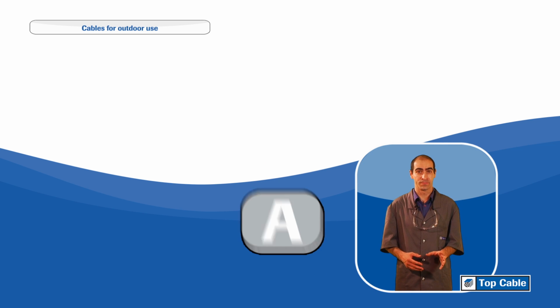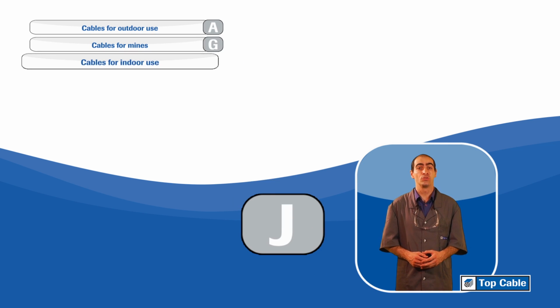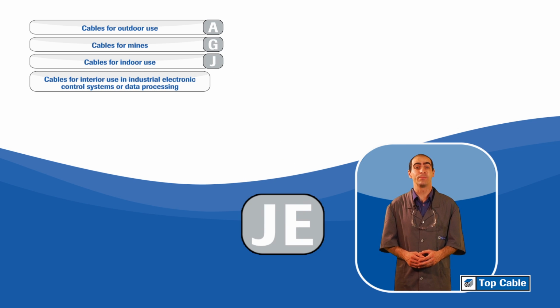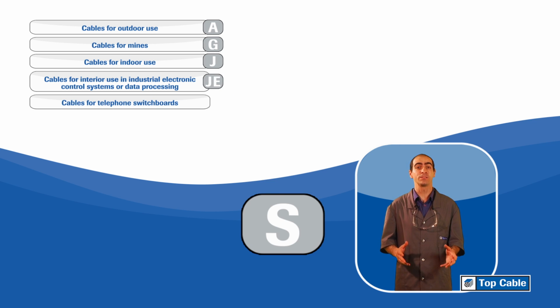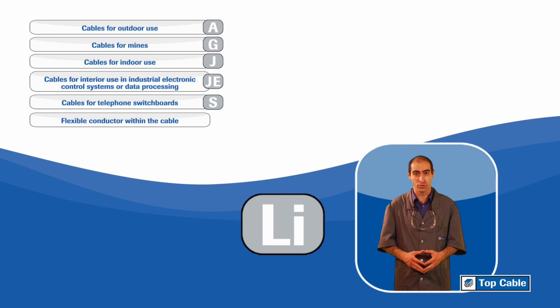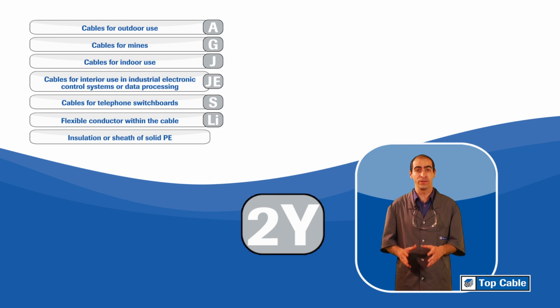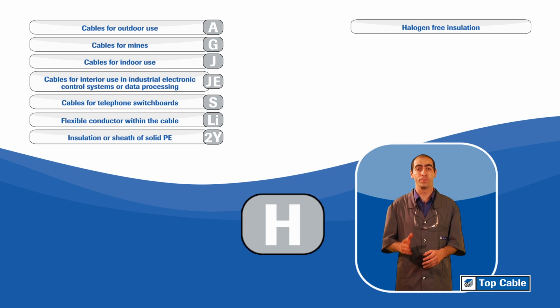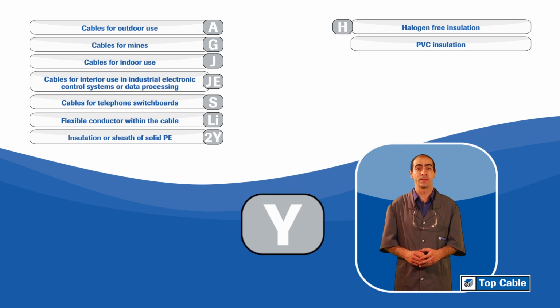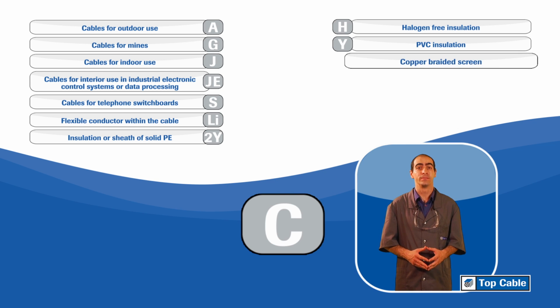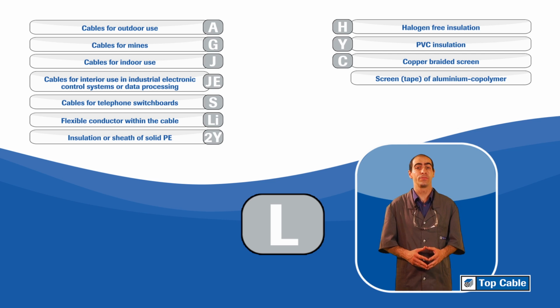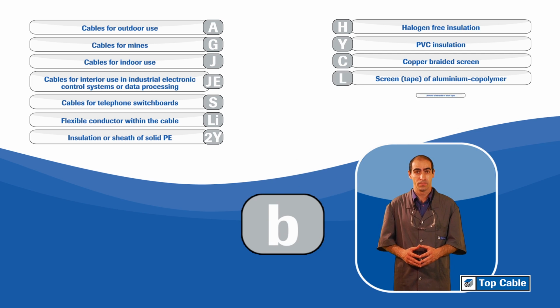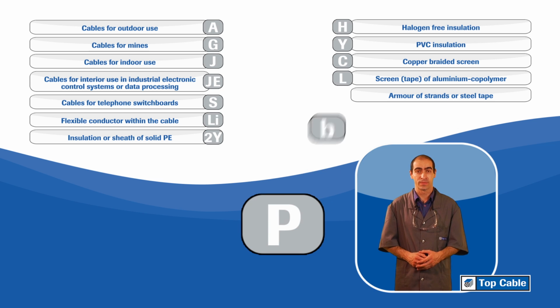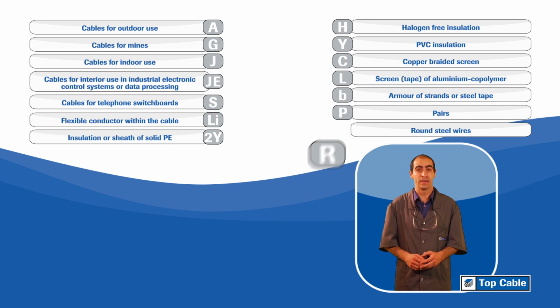The most common letters mean: A, cables for outdoor use. G, cables for mines. J, cables for indoor use. JE, cables for interior use in industrial electronic control systems or data processing. S, cables for telephone switchboards. LI, flexible conductor within the cable. 2Y, insulation or sheath of solid PE. H, halogen-free insulation. Y, PVC insulation. C, copper braided screen. L, screen tape of aluminium copolymer. B, armor of strands or steel tape. P, pairs. R, round steel wires.